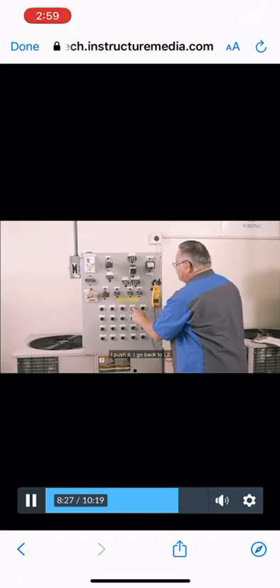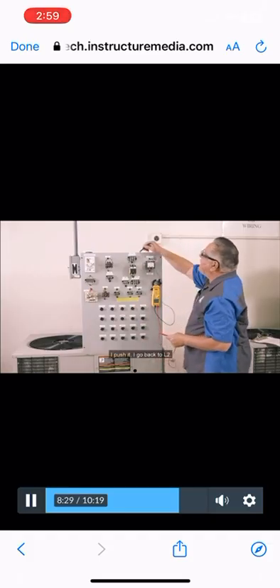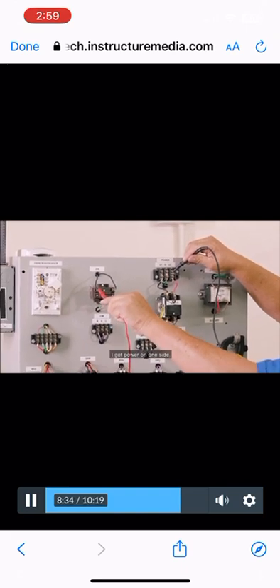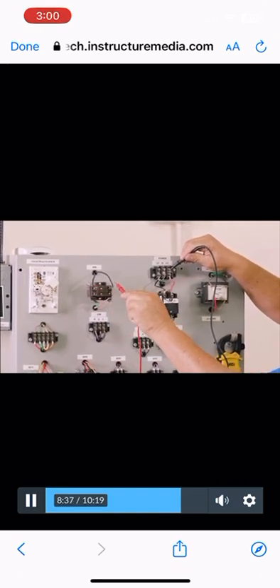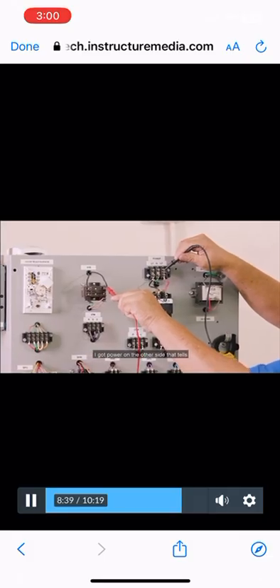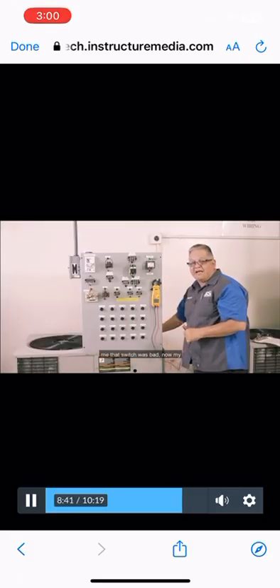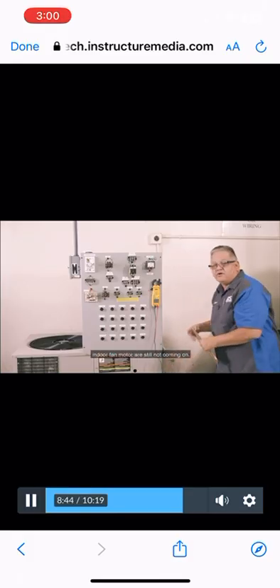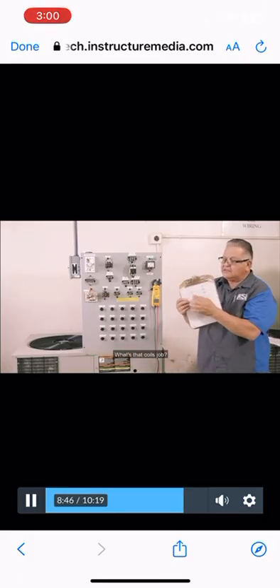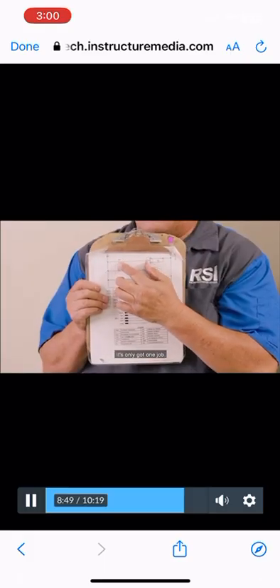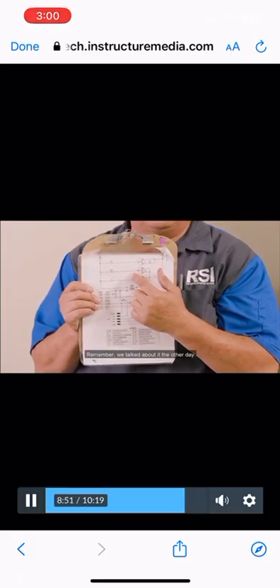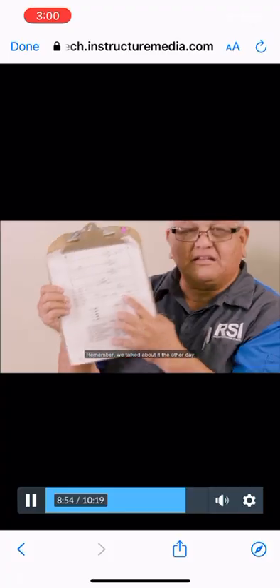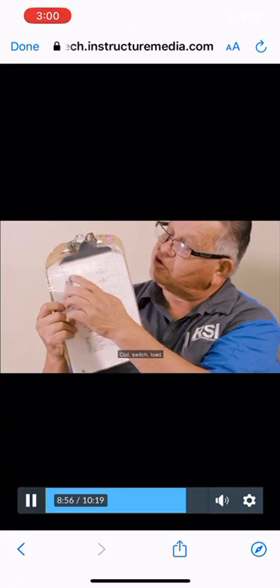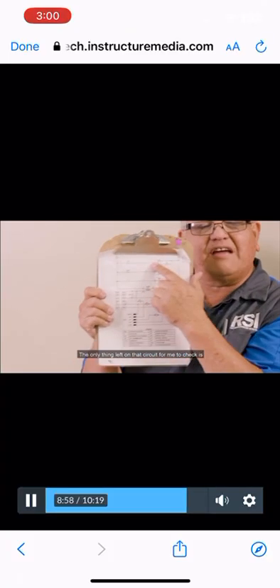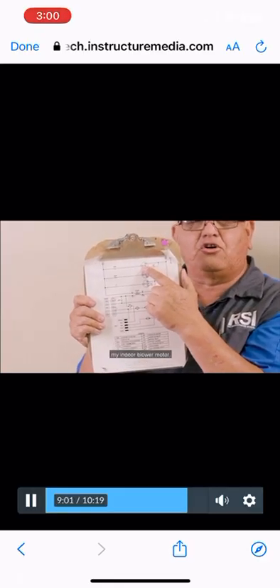So let's fix it. I push it. I go back to L2. I go across my switch. I got power on one side. I got power on the other side. That tells me that switch was bad. Now, my indoor fan motor's still not coming on. What's that coil's job? It's only got one job: energize the load. Remember, we talked about it the other day. Coil, switch, load. The only thing left on that circuit for me to check is my indoor blower motor.